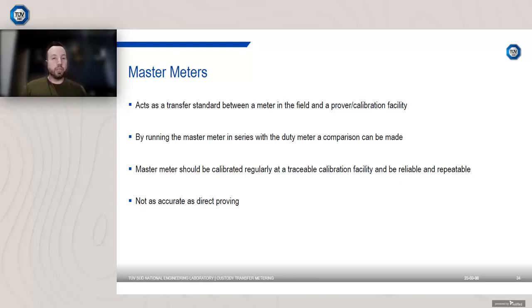I'm just going to finish this section on master meters. So although they're not provers, they can be used to prove a flow meter. So they act as a transfer standard between a meter in the field and another prover or, say, a calibration facility. So by running the master meter in series with your duty meter, you can make the comparison. It's obviously not as accurate as direct proving, but it does have its advantages.